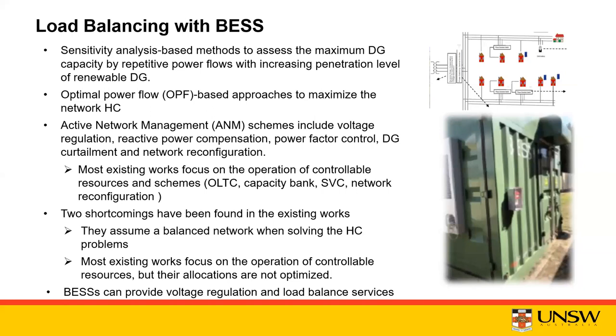We use active network management schemes, including voltage regulation, reactive power compensation, power factor control, DG curtailment, and network reconfiguration. For voltage regulation on transformers, as I mentioned earlier, in many cases it has already reached the limit, already at the upper or lower level of tap-changing transformers, so you can't do much.